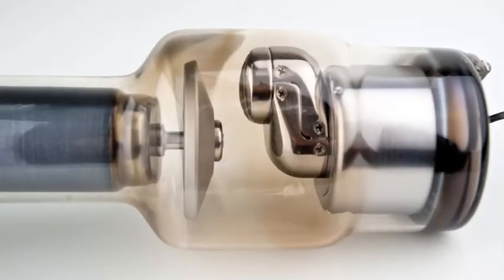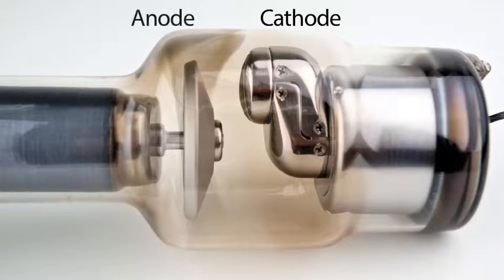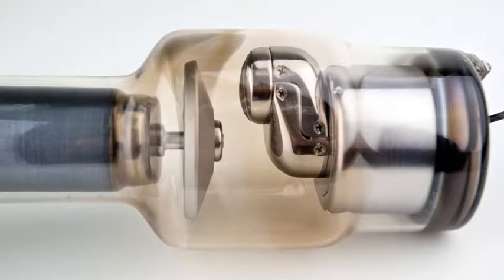The X-ray tube used in diagnostic radiography consists of a negatively charged cathode that emits a high-powered stream of electrons towards a rotating positively charged anode. The electrons react with the atoms of the anode, creating X-ray photons that are directed through a glass window towards the subject to be imaged. The original stream of photons produced is called the incident X-ray or primary beam.